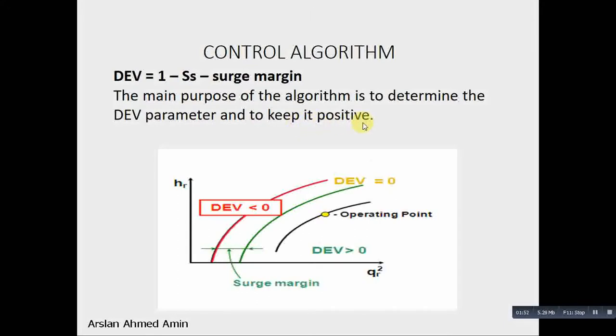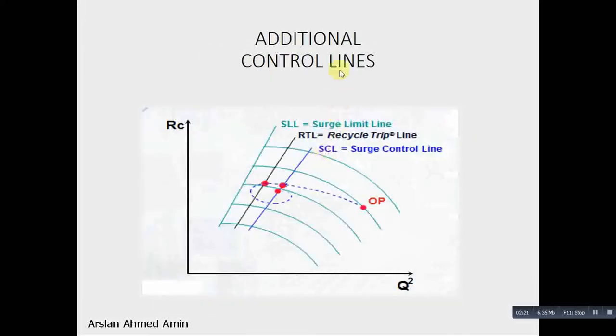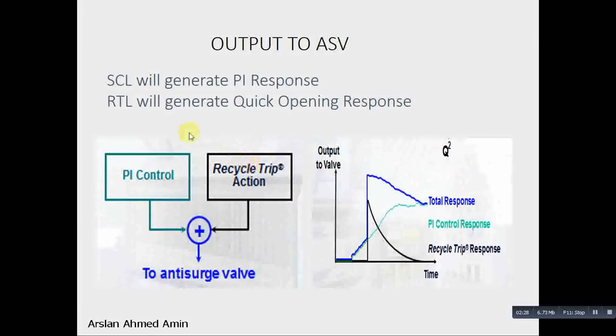Now deviation is equal to 0 on our desired line. And the deviation is positive in the green zone or the safer zone, and the deviation is negative on the left side. So the algorithm keeps the deviation parameter positive by opening the recycle valve. The surge controller will generate the PI response and recycle trip line will generate the quick opening response. And the total response would be PI control plus recycle trip protection.